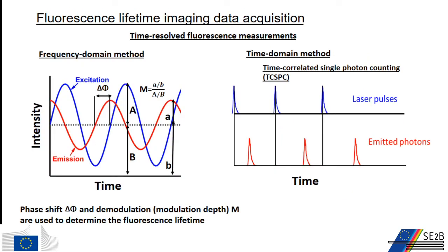Fluorescence lifetime of a fluorophore is commonly determined using frequency domain and time domain data acquisition techniques. Both techniques are quite different in electronics and data acquisition methods. However, mathematically both are equivalent and through Fourier transform, data from one technique can be converted to the other. In the frequency domain method, the intensity of the continuous wave source is modulated at a high frequency up to 100 MHz. Due to this modulation, the fluorescence from the specimen is also modulated at the same frequency, but the emitted signal is phase shifted due to the delay in fluorescence. The fluorescence lifetime is calculated from the phase delay and modulation depth information.